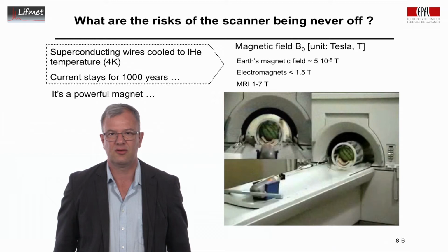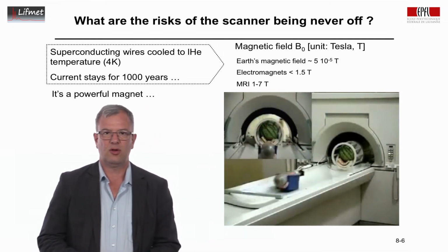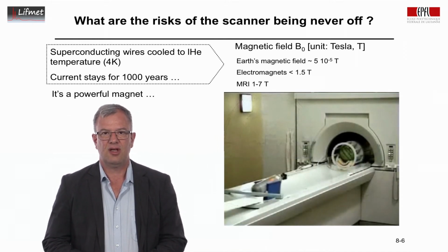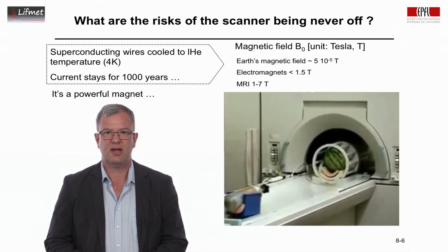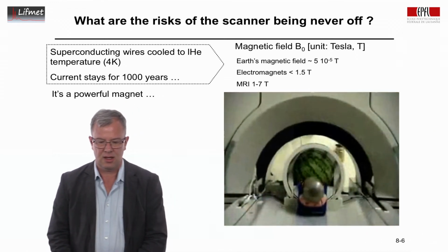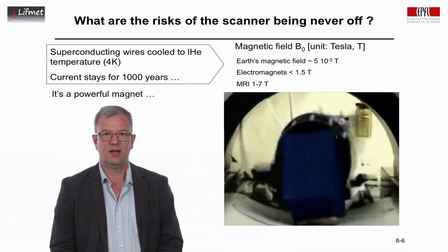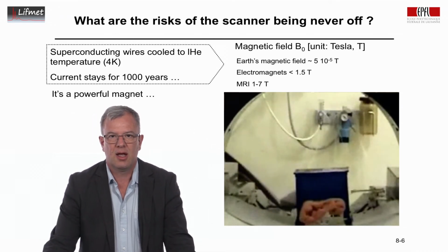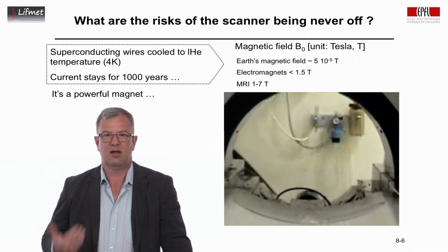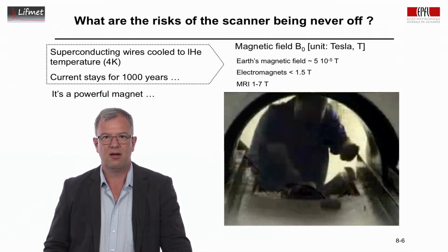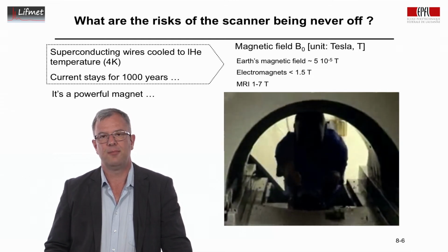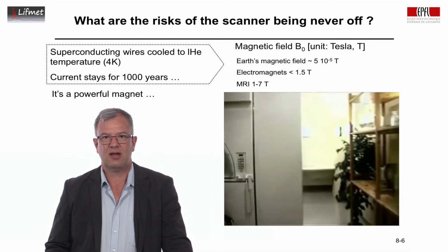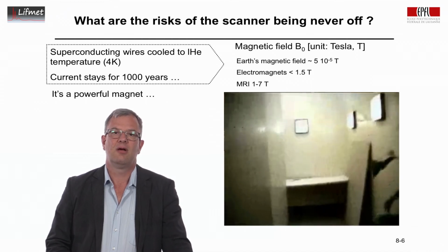You have lots of oxygen bottles in the hospital. They're placing this bottle on the patient bed. And as you can see on the patient bed, instead of putting a patient, they're putting a watermelon as our subject inside the RF coil where the head would be. The experiment that was done here is to illustrate what happens if a magnetic object is put too close to the magnet and starts to get attracted by the magnet.